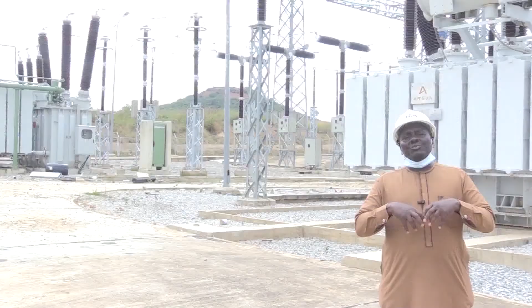The official at the Jos transmission station further spoke on the impact of the reactors: we don't want voltage to be above the designed capacity of our equipment, and also at the receiving end. The receiving end tends to complain that voltage is always high at their end. So we use this to suppress, even though one reactor is only suppressing about 20 kV. So if you have about 360, you just reduce by 20 kV, you see you have not done much, you still need more. That is why the second one is coming in.